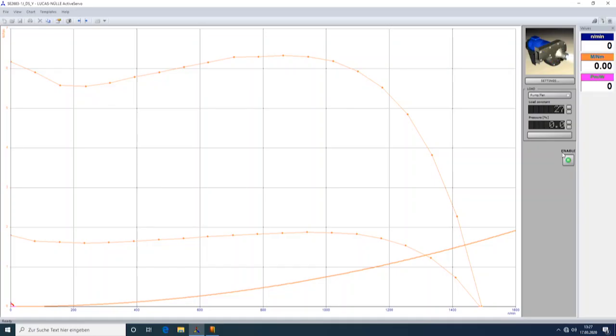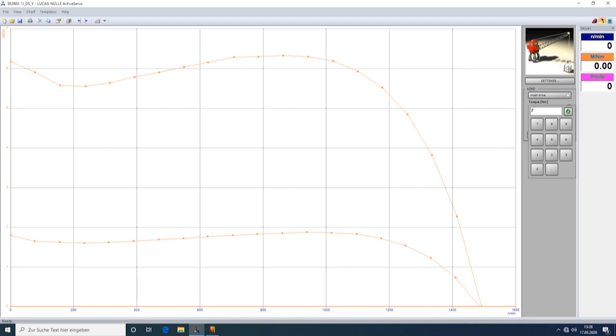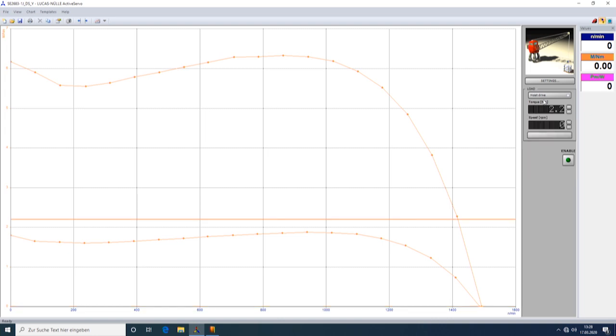Let's try one other example. I will move to another working machine like a hoist drive, which could be a normal tooling machine in the industry. And if I look at the motor nameplate, I see, okay, this motor has a value of approximately 0.37 kilowatt. And so the torque should be around 2 and something Newton meters. So I applied here a value of 2.2 Newton meter for the torque.